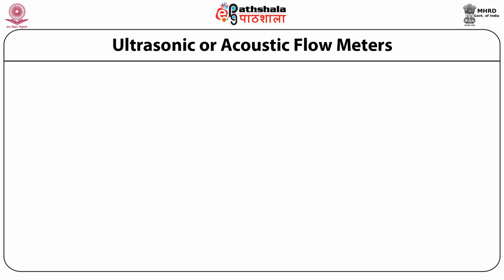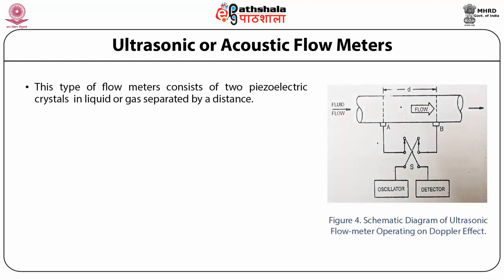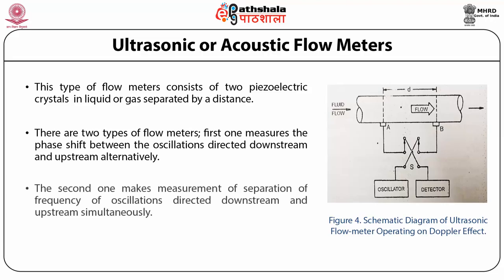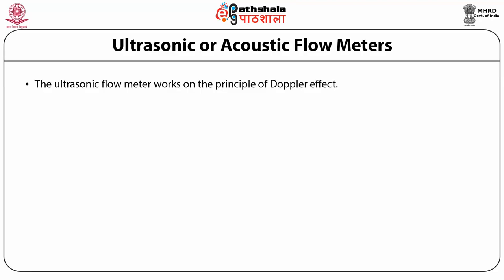Ultrasonic or acoustic flow meters consist of two piezoelectric crystals in liquid or gas, separated by a distance. One crystal works as a transmitter and the other as a receiver. There are two types: the first measures the phase shift between oscillations directed downstream and upstream alternately; the second measures the difference in frequency of oscillations directed downstream and upstream simultaneously. The schematic is shown in figure 4. The ultrasonic flow meter works on the principle of the Doppler effect.